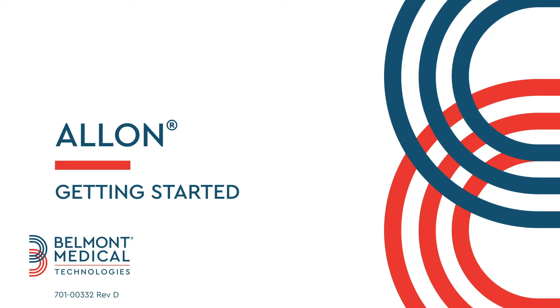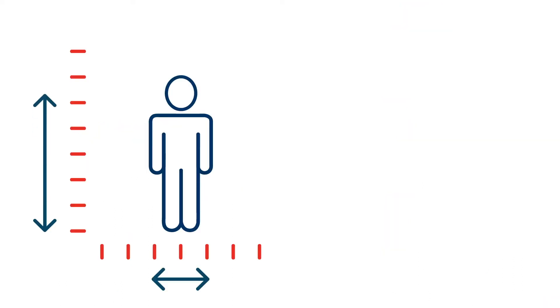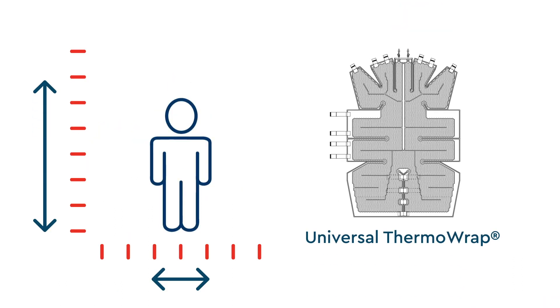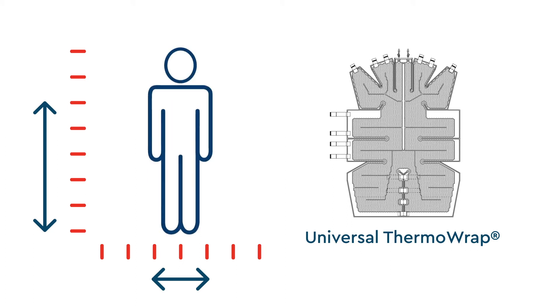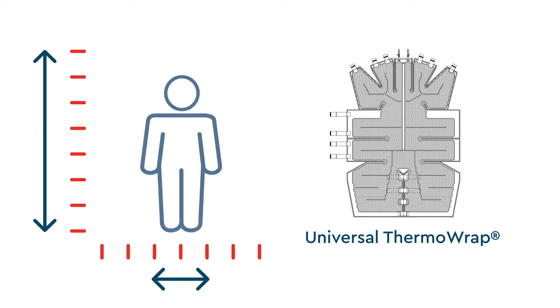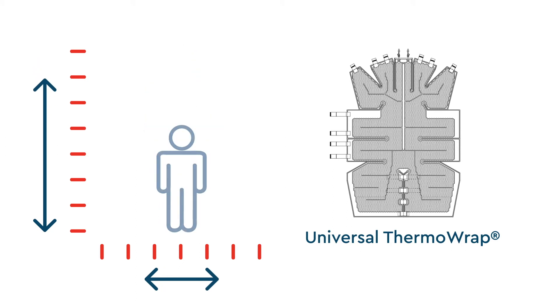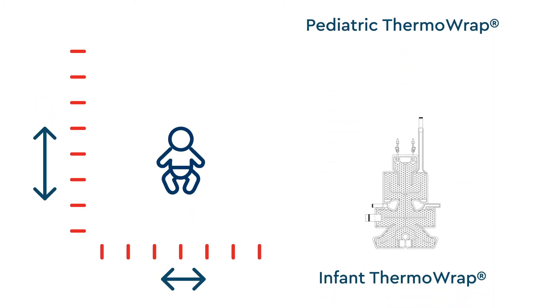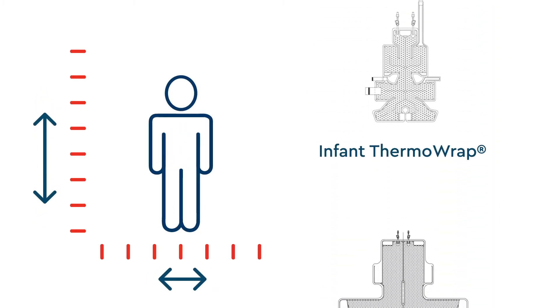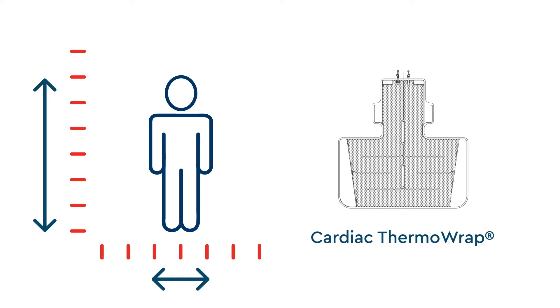Let's review the basic operation of Allon. First, choose the appropriate ThermoWrap for the procedure according to the patient's size and type of surgery. We provide adult, pediatric, and infant ThermoWraps in different sizes as well as a specialized cardiac wrap for cardiac surgeries.